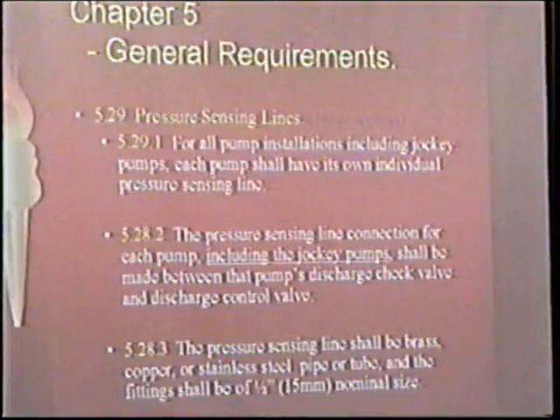it's pretty specific on how they're supposed to be installed, and there are very good reasons why they should be installed this way, so we're glad to see that it got moved into the code. This is probably one of the biggest things we still see out in the field with problems on field installations, having the sensing lines either not piped from the right spot on the pipe, or the check valves aren't installed right, that sort of thing.